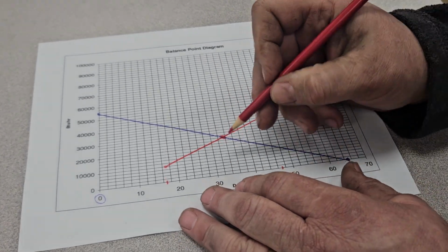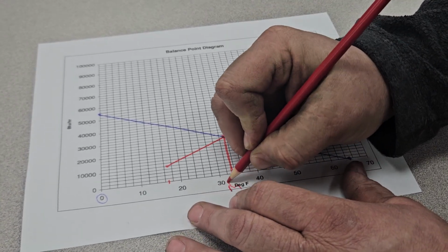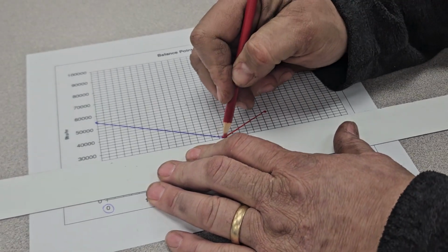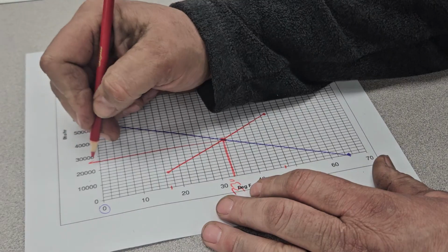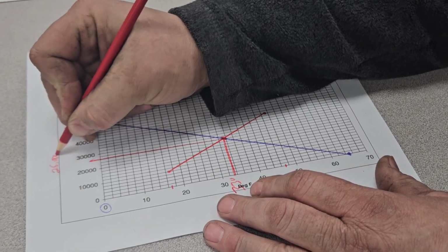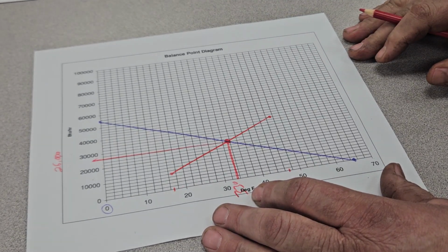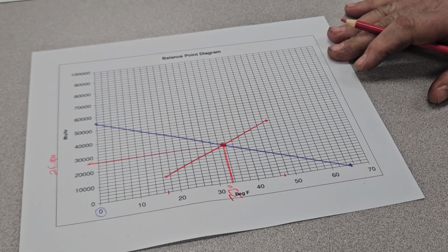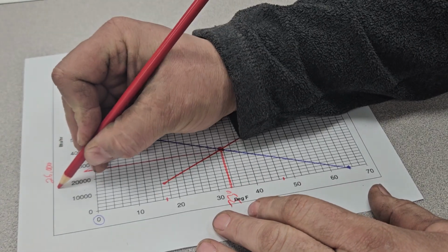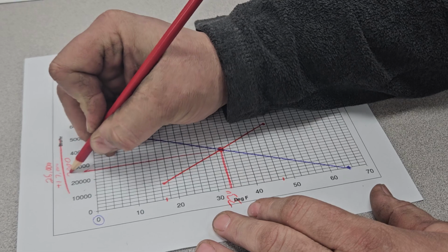Now we can say that the balance point is at roughly 33 degrees, and the BTU output of that heat pump over there is 26,000 BTUs. So that's what we'll say the balance point is on this diagram.